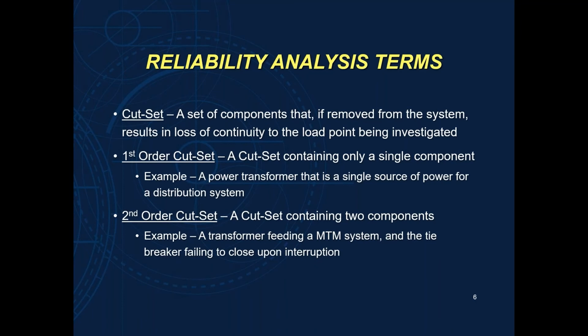So as an example, I'll put in here, if you have a radial fed system that has one power transformer that supplies, say, an MCC with some motors on it, if you lose that transformer, you lose all the MCC, you lose all your load. A single transformer failure in that instance would cause an outage. So that would be considered a first order cut set. A second order cut set would be any cut set that has two components. So for instance, again, I have an example here. If you have a transformer feeding a MCC and you have a main tie main system, so you have redundant transformers on either side, you lose one transformer, but then say your tie breaker trips, well, then you're going to lose one side of your bus, and that's going to be considered an outage. So that would be an example of a second order.